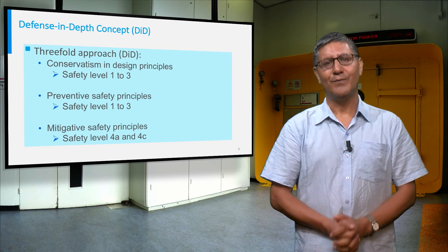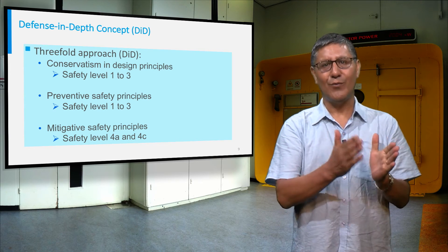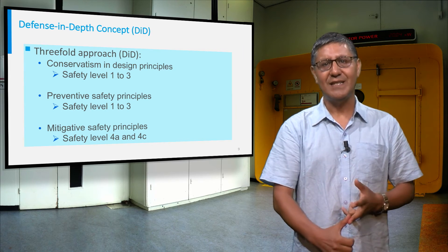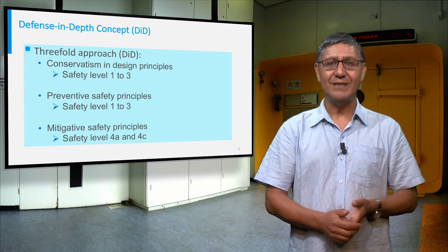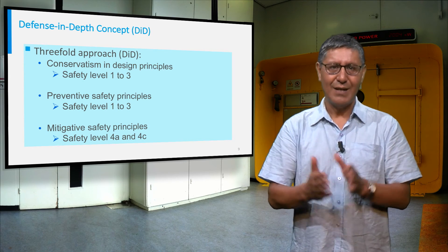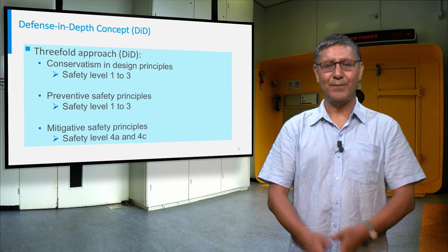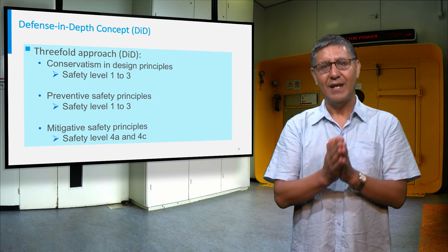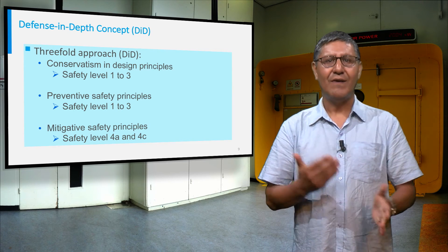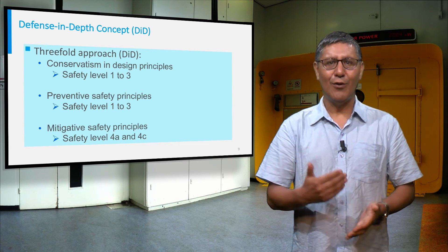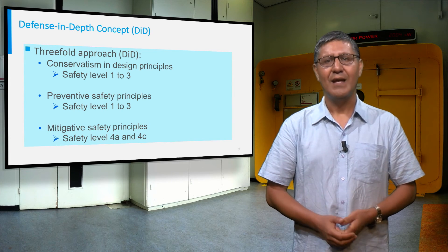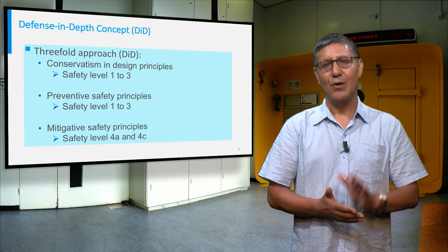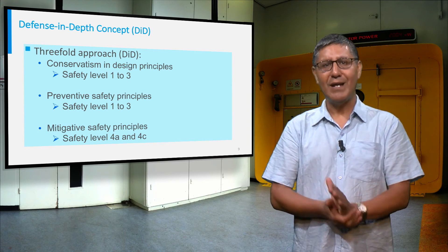Safety levels are defined from one to four: normal operation, operational occurrences, design basis accidents, and beyond design basis accidents. For each safety level, a protection goal is defined. Next, the systems foreseen to cope with the event at each safety level are listed, and the procedures developed for each safety level are defined. Safety levels one to three are purely preventive, while level four is mainly mitigative.